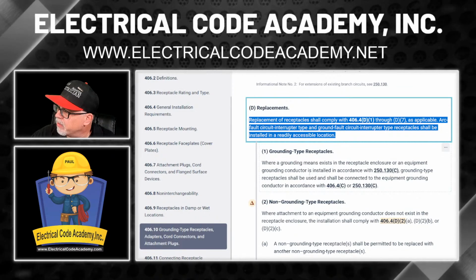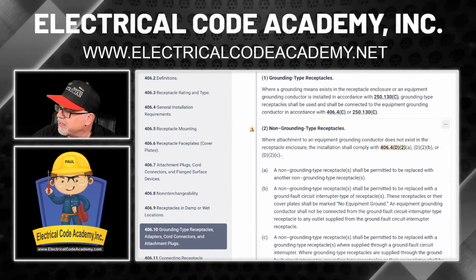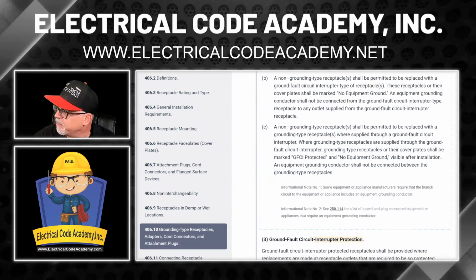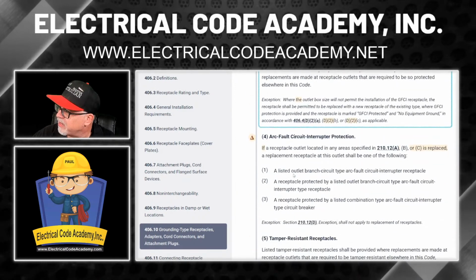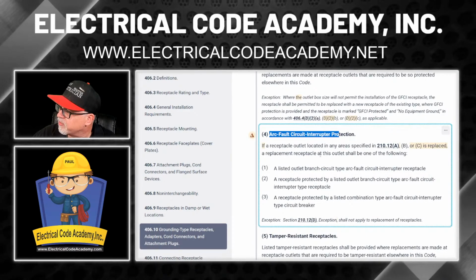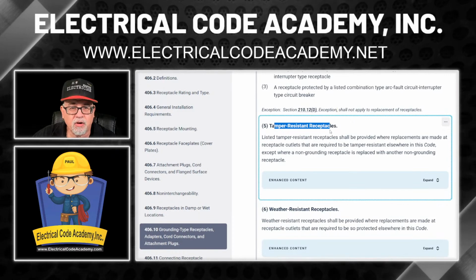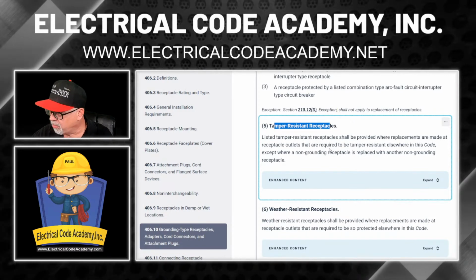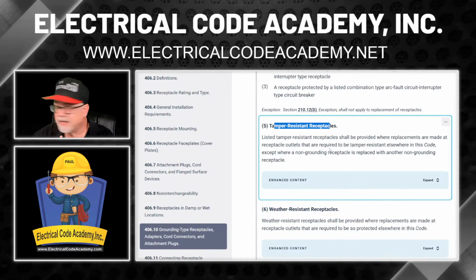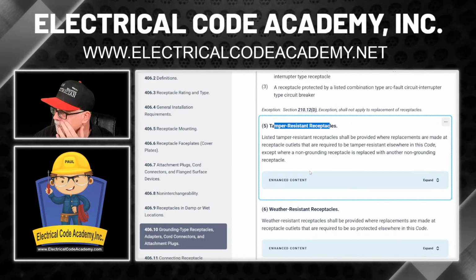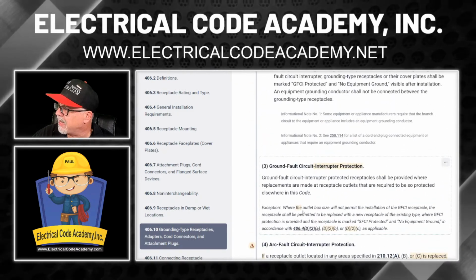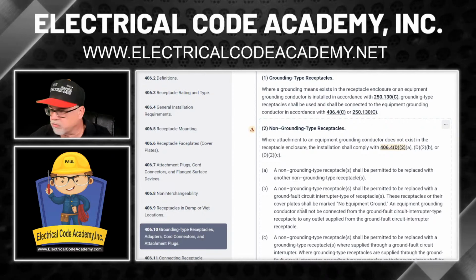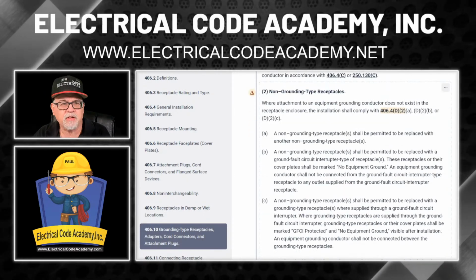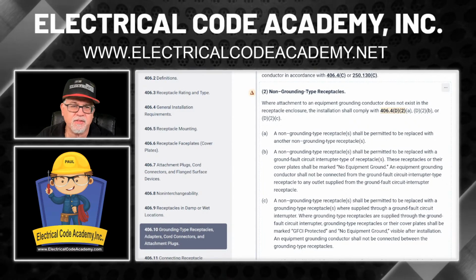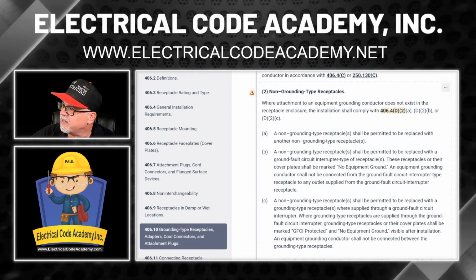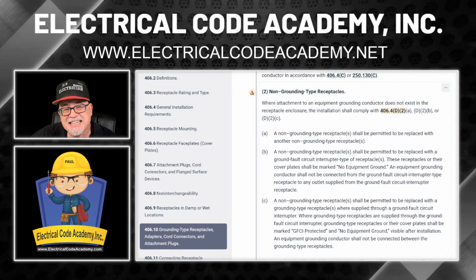Okay, so I will show you real quick. There's D1. We're going to be looking at D2 because this is originally a non-grounded type. But just to show you, there's rules for D3. That's for GFCIs. Here's rules for D4 if you have AFCI. Here's a rule for tamper resistant. So if you're removing a receptacle in a location that now requires tamper resistant, then guess what? It's got to be tamper resistant, okay? You're putting it back, okay? So again, just laying out those rules. All right, so let's deal with his real quick. So non-grounded type. You see that we have an A, B, and a C there. So we're at 406.4D, and there's a D2A, a D2B, and a D2C.